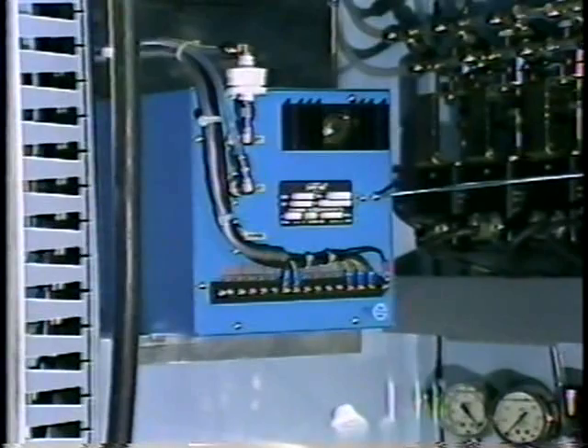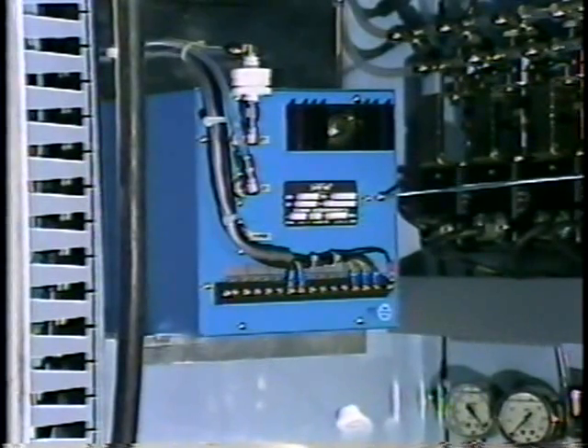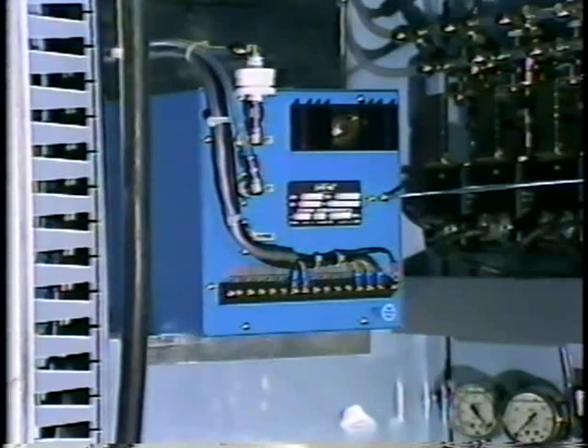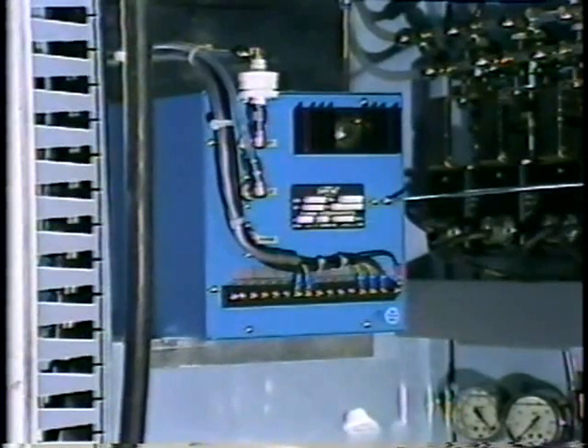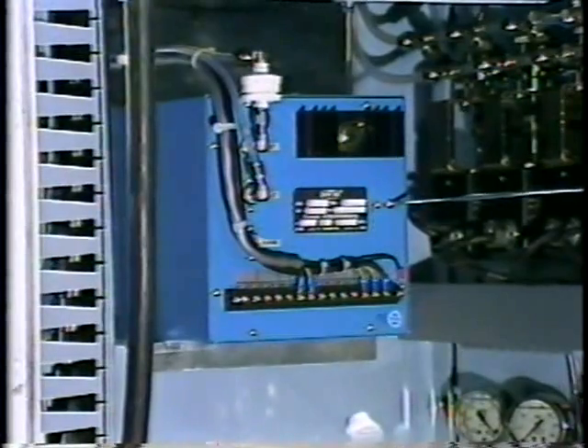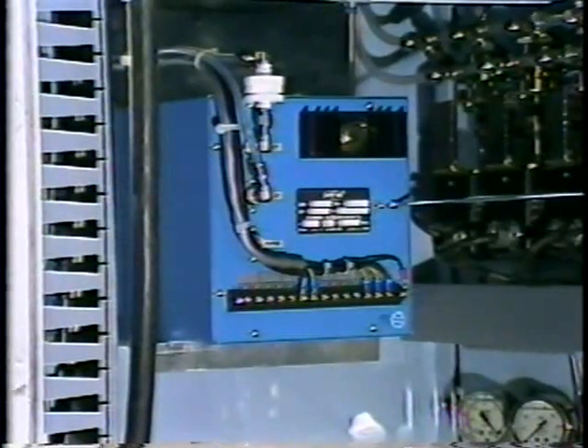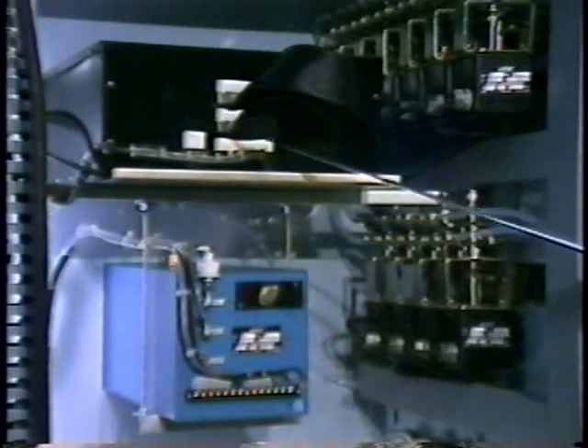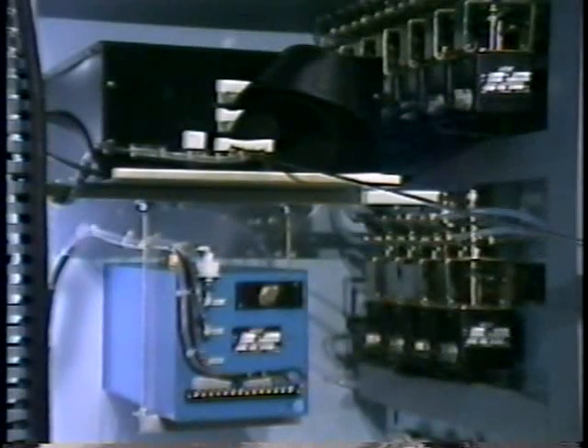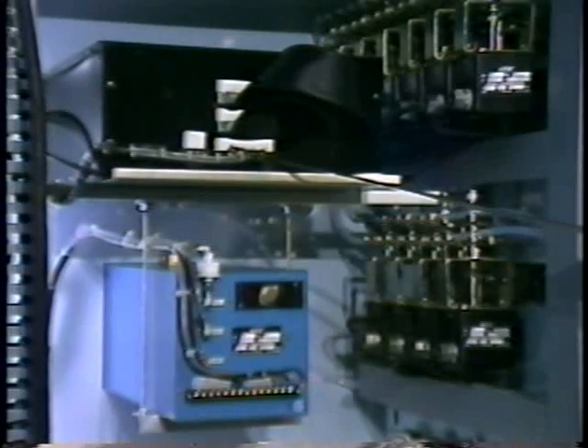The analyzer is of non-dispersive infrared design, utilizing the latest technology microflow detector to measure the absorption of infrared energy at the 4-micron wavelength. While completing the sampling cycle and interpreting the results, the computer simultaneously controls the preparation and cleansing of the other probes in line for sampling. This specialized sampling scheme solves critical problems unique to sampling in pulverized coal systems.